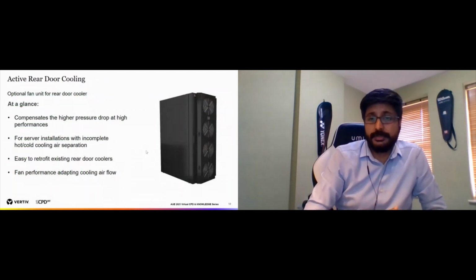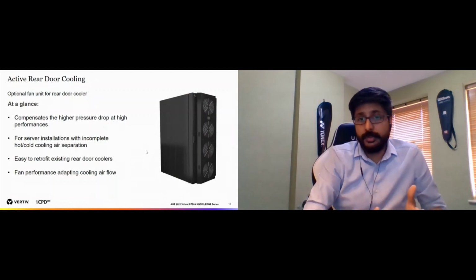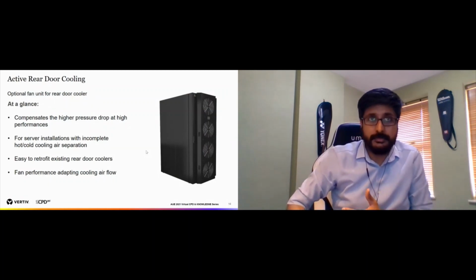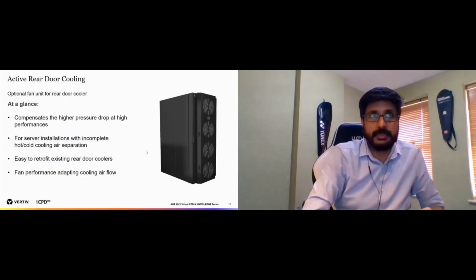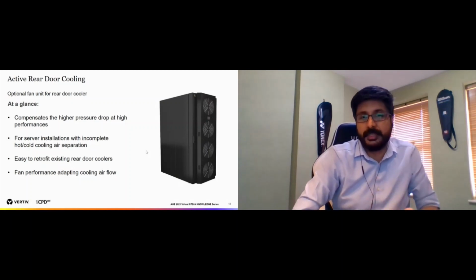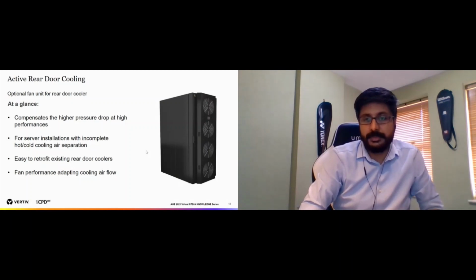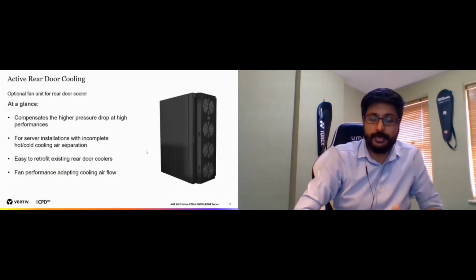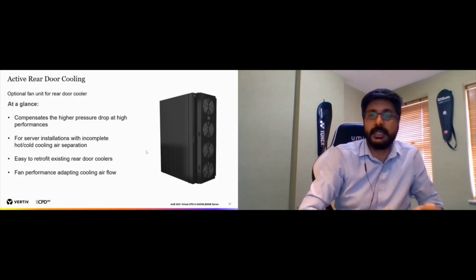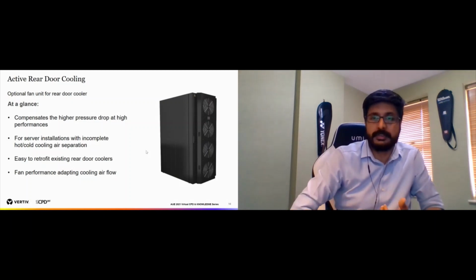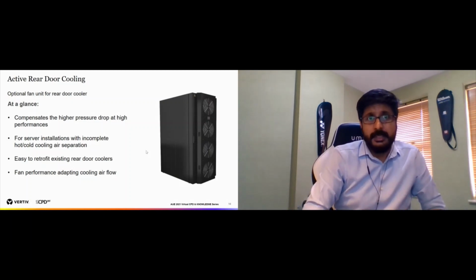Moving on to the active rear door cooling. This is basically a plugin that we can have on the passive, if there is heat leakage within the servers, or if you need to get more capacity out of the passive rear door cooling. Then you can have these additional fan modules fitted onto the passive to give you the active rear door cooling, which brings your capacities up to 50 kilowatt as well.